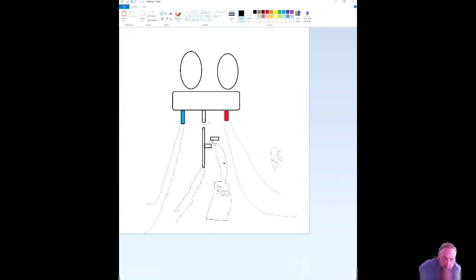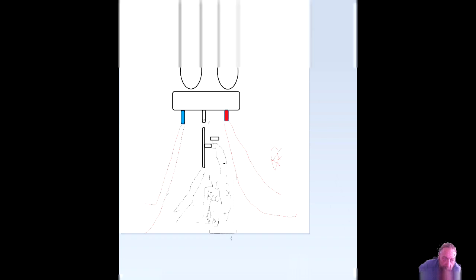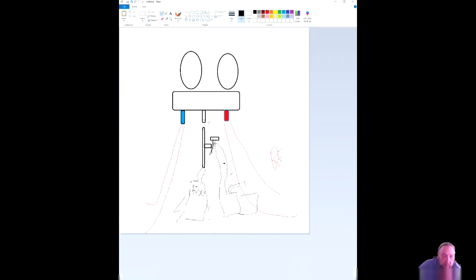You'd have a piece here and a T fitting here, and I have a manual shutoff valve right here. I'll hook up a shutoff valve to this unit. There's a valve there, and this would go to my micron gauge. Let's say that's my reading, 500. And then this goes to the refrigerant system.